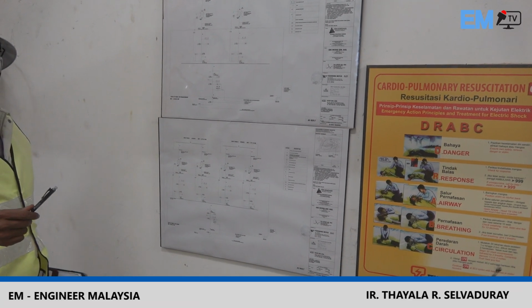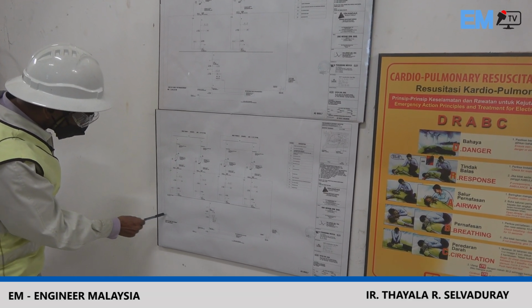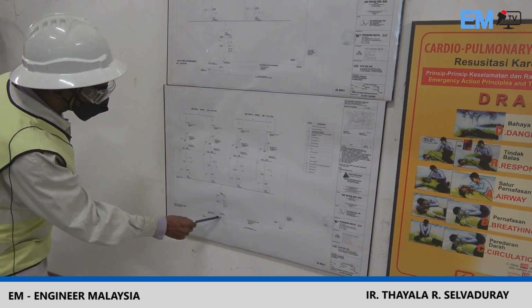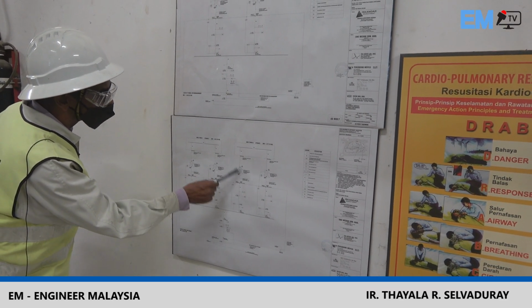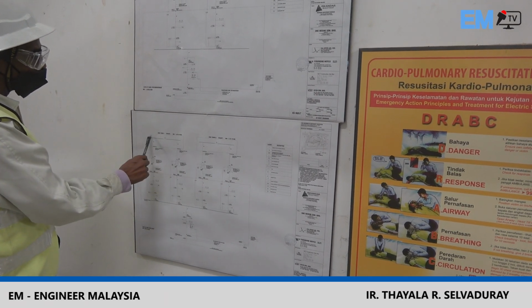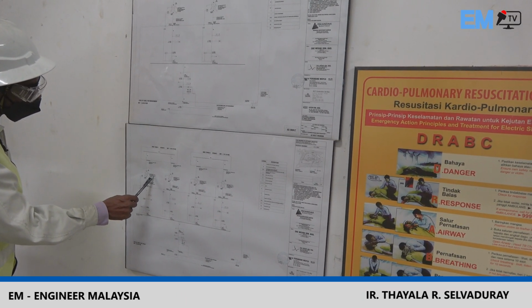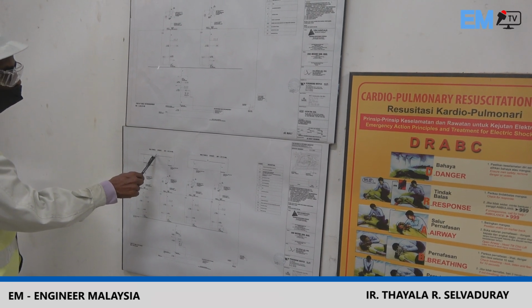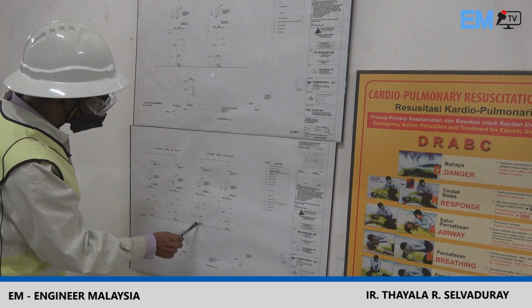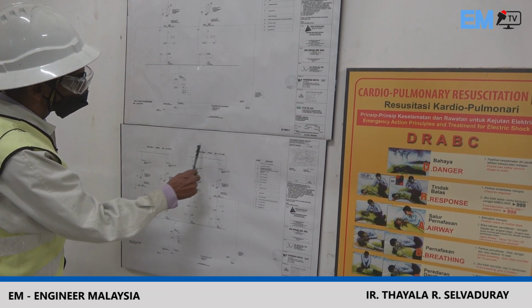And then similarly, this is also a different set of supply for the tenant. You can see here tenant, right? The tenant supply is here, and the TNB supply comes here at 33 kV with the protection circuits here, going out to 4 transformers. In other words, going to different blocks. Tower 1 is here and Tower 2 is here. Right? Again, Tower 1 and Tower 2 are also split in different areas. So you've got the transformer here, stepping down from 33 kV to 433, going through breakers and then going out to the switchboard rooms, the main switchboard room, which I'll show you later. Likewise, the other 2 transformers are the same thing. They're going to Tower 2, broken down into 433 volts to the main switchboard.